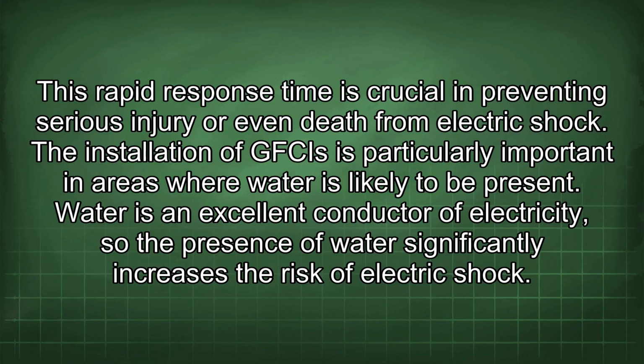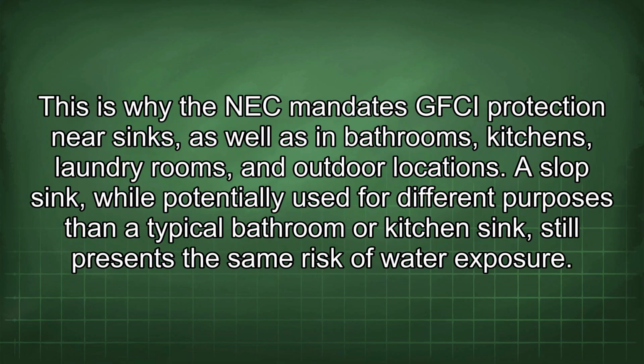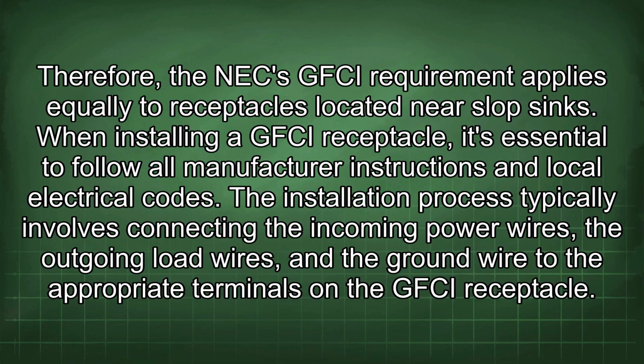The installation of GFCIs is particularly important in areas where water is likely to be present. Water is an excellent conductor of electricity, so the presence of water significantly increases the risk of electric shock. This is why the NEC mandates GFCI protection near sinks, as well as in bathrooms, kitchens, laundry rooms, and outdoor locations. A slop sink, while potentially used for different purposes than a typical bathroom or kitchen sink, still presents the same risk of water exposure. Therefore, the NEC GFCI requirement applies equally to receptacles located near slop sinks.